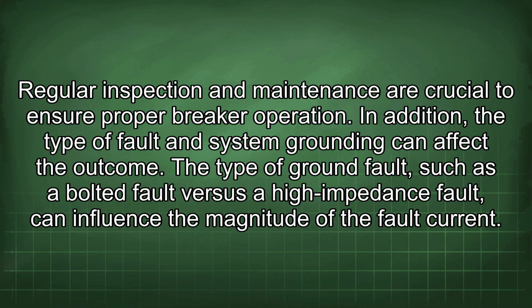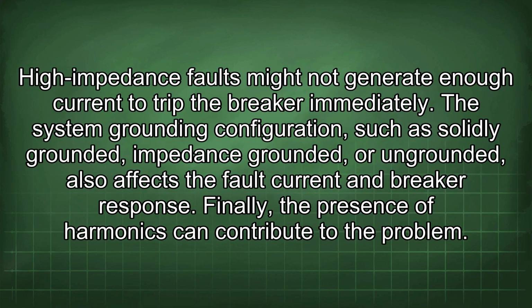The type of ground fault, such as a bolted fault versus a high impedance fault, can influence the magnitude of the fault current. High impedance faults might not generate enough current to trip the breaker immediately. The system grounding configuration, such as solidly grounded, impedance grounded, or ungrounded, also affects the fault current and breaker response.